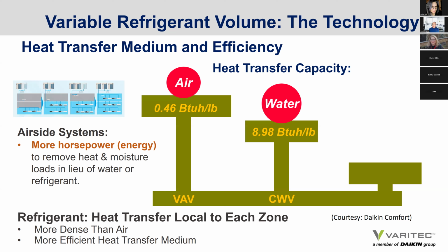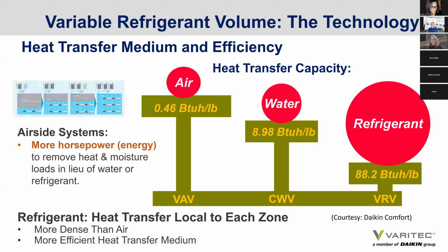Well, there is another heat transfer medium, refrigerant. Refrigerant is an even more dense heat transfer medium, and it can move 88.2 BTUs per pound of refrigerant. Consequently, you can move even that much more energy with refrigerant. So if you can bring refrigerant locally to each zone in a building and have that refrigerant absorb the energy gain within the spaces, you can move that energy out of a building more efficiently, conceptually, than water, but that begs some evaluation, but certainly more so than air.